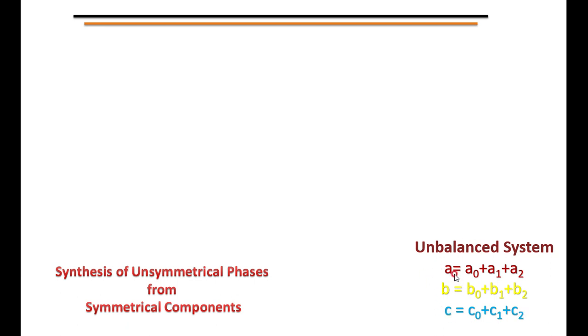An unbalanced phasor can be resolved into its symmetrical components as a0, a1, a2, b0, b1, b2, c0, c1, c2. For voltage: VA decomposes into VA0, VA1, VA2; VB into VB0, VB1, VB2; VC into VC0, VC1, VC2. Applied to current: IA equals IA0 plus IA1 plus IA2; IB equals IB0 plus IB1 plus IB2; and similarly for phase C.